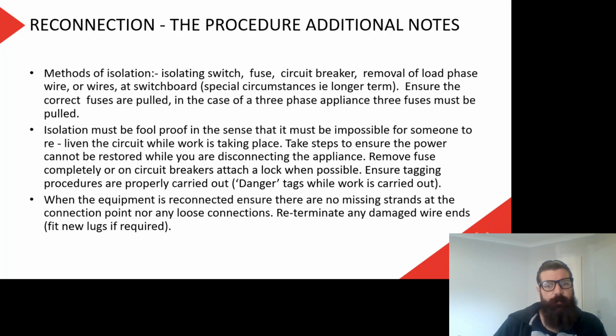So a couple of additional notes here. Methods of isolation, same as we talked about before. Isolation must be foolproof. That means that we physically lock it out in some way to prevent that from being re-enabled, just like we talked before. And as we said on the last one, make sure that our reconnections are done properly, that all of our physical wire connections are good.